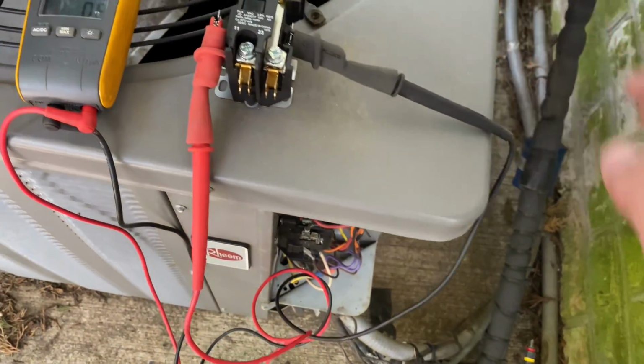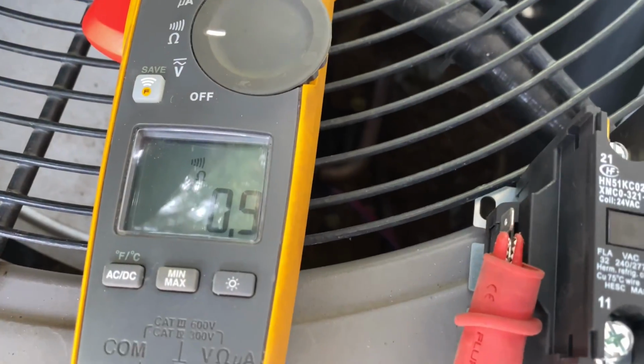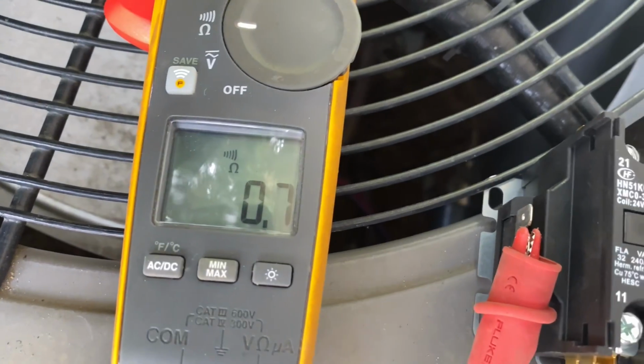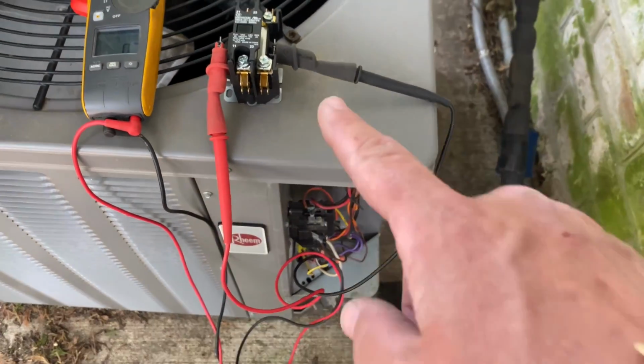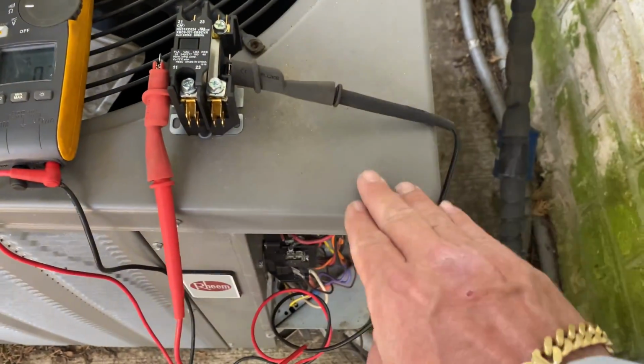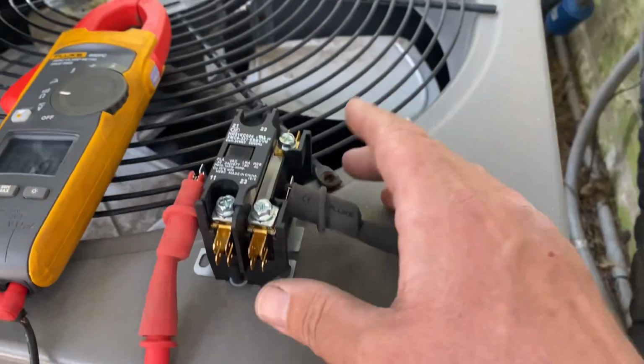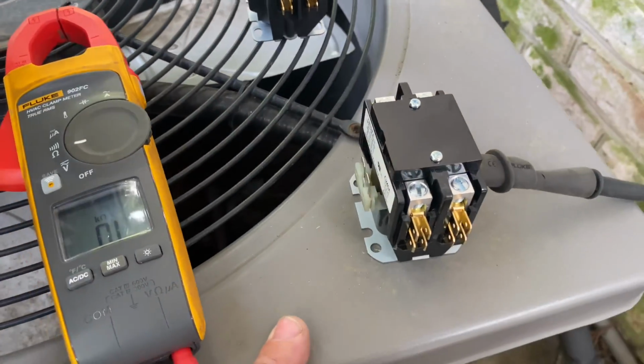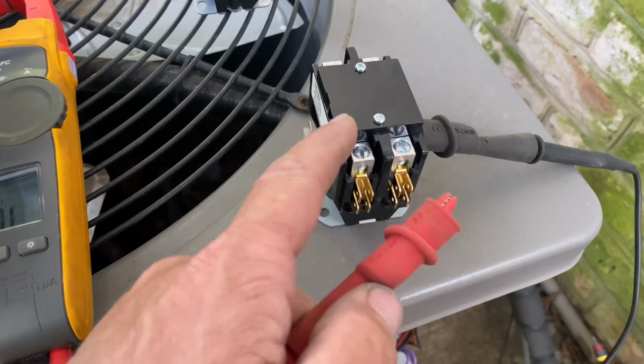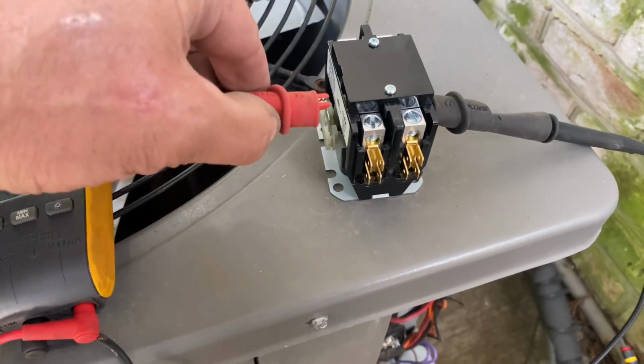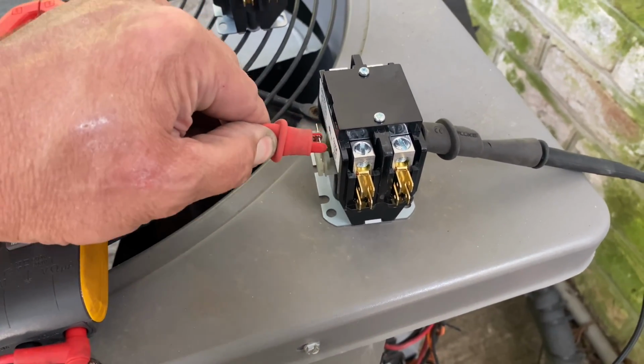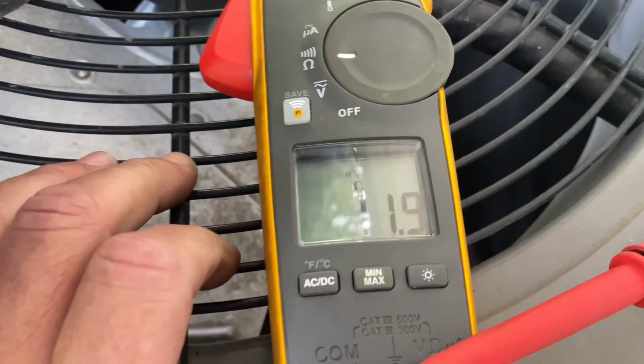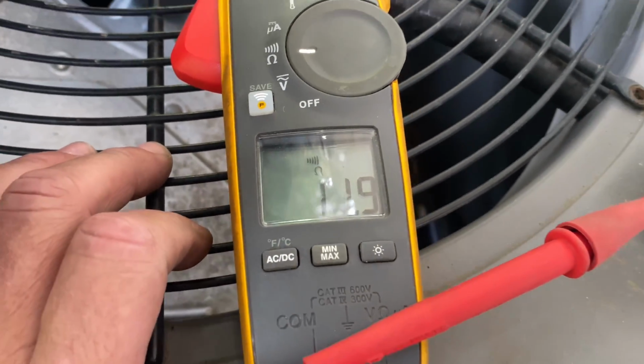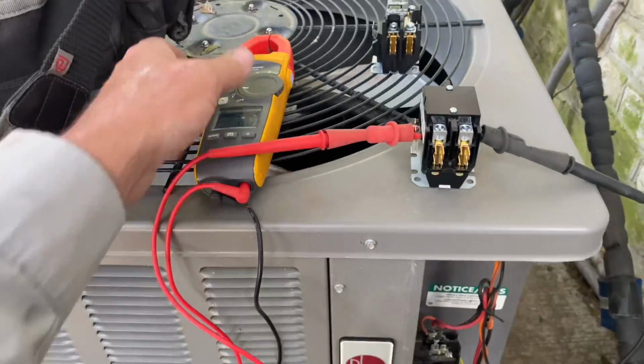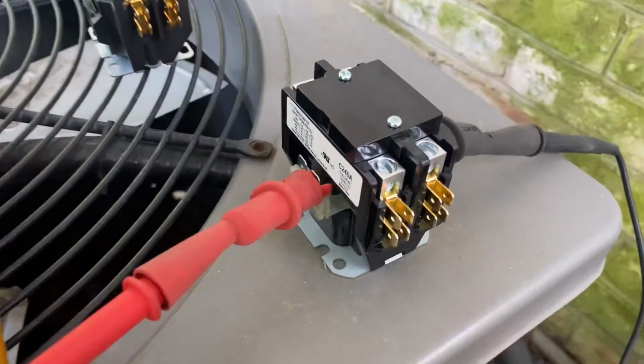Okay, and you're gonna see that we have 0.9, 0.8, 0.9, 0.7. The 24 volt coil, the windings on this contactor, no bueno. It needs to be much higher. Here is a brand new 2-pole contactor, and we're gonna hook up our leads to that. And you're gonna see we have 11.9, 12. Anywhere over 10 to as high as 20 is acceptable. That means the coil is good.